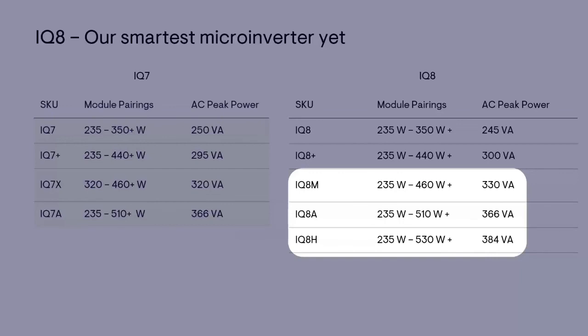If the IQ8s are not part of the equation, if you're just installing a generator and batteries with M250s on the solar array, then you would have to use load shedding to turn off all of the M250s when the generator is operating.